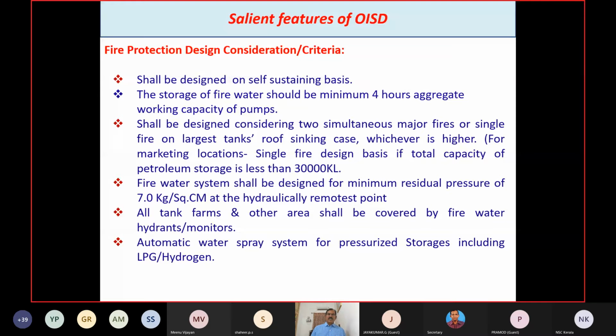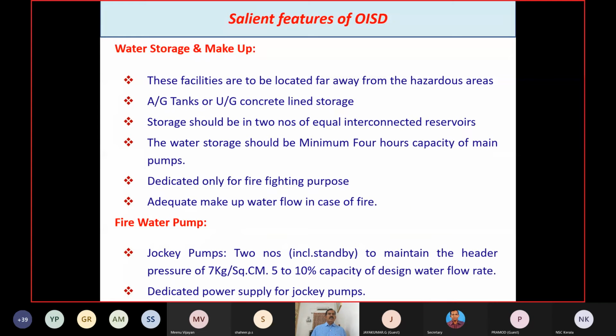Then the fire water system shall be designed for a minimum residual pressure of 7 kg per cm square at the hydraulically remotest point. So all tank farms and other areas shall be covered by fire water hydrants and monitors. An automatic water spray system is provided for pressurized storages, including LPG and hydrogen storages. Water storage and make up: these facilities are to be located far away from the hazardous area, mostly in the perimeter of the industry, so that any backup facility may also be available for unloading of water tankers, etc. So it can be either above ground tanks or underground tanks of concrete lined storage. The storage should be in 2 equal interconnected reservoirs, because if one tank is taken for maintenance, the other tank will be available.